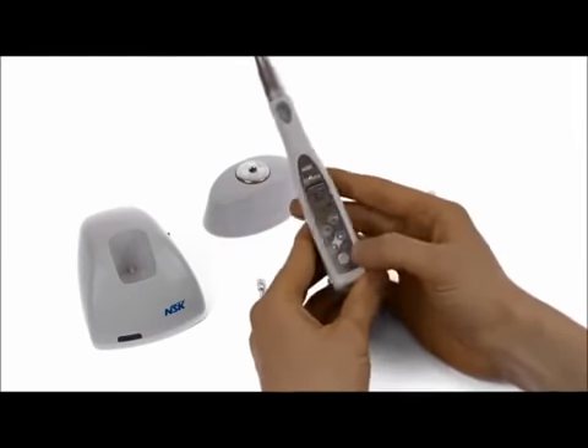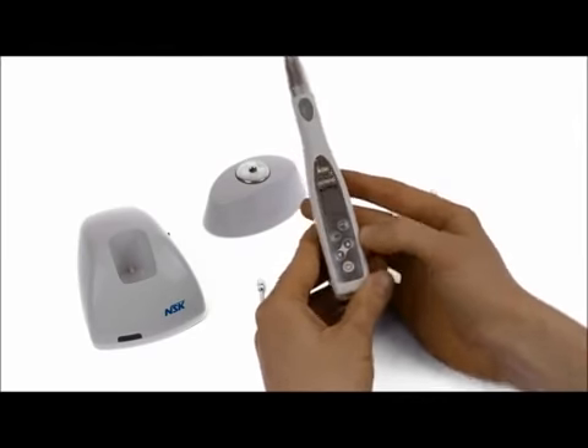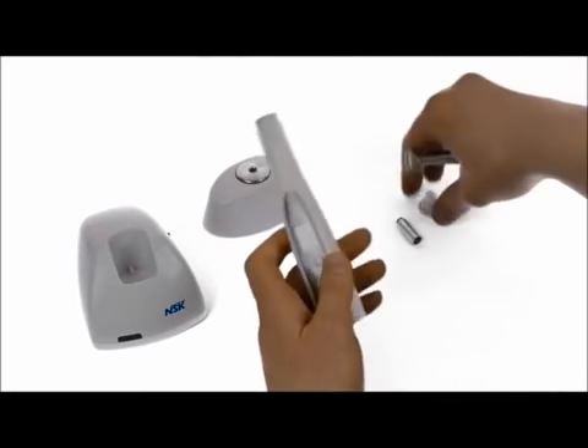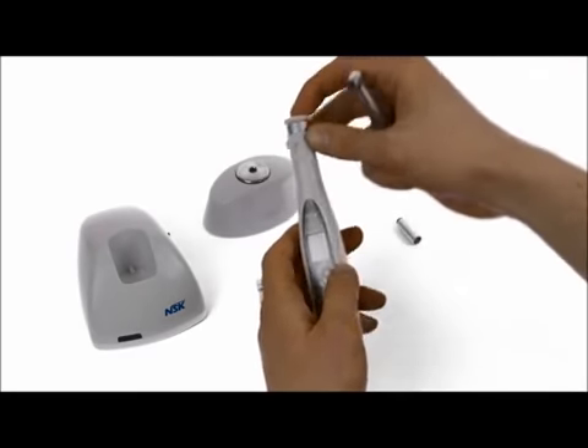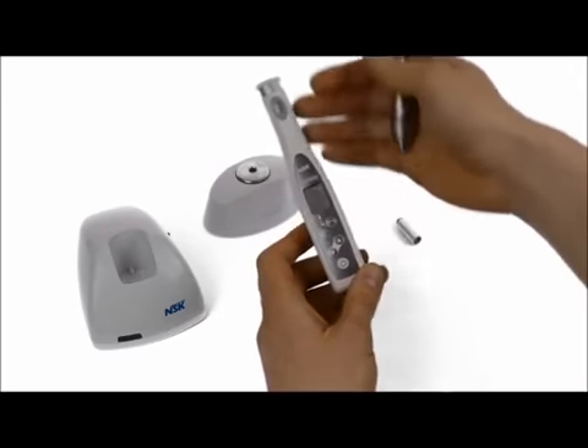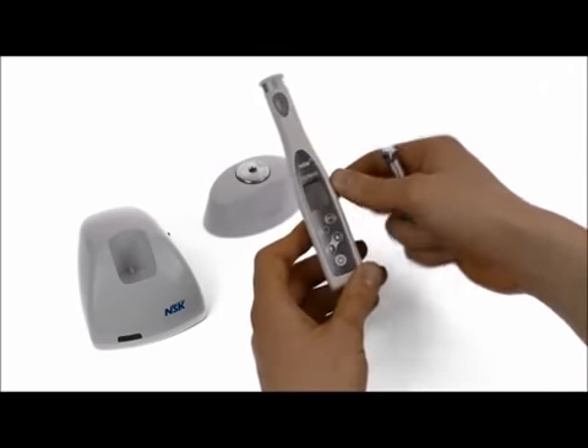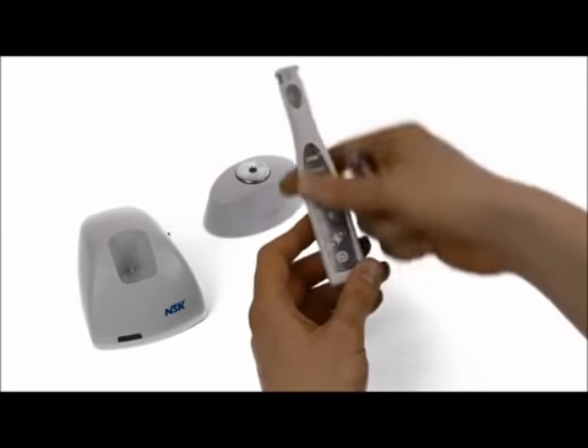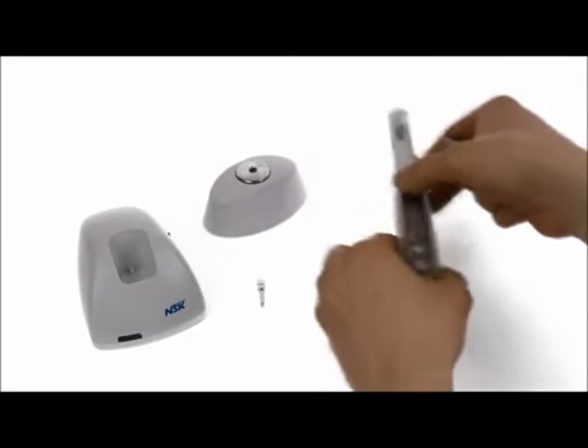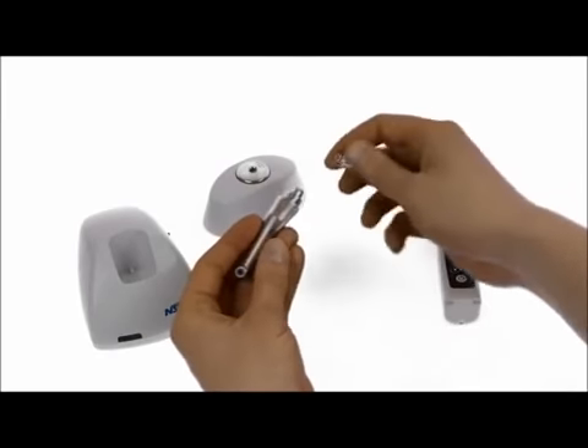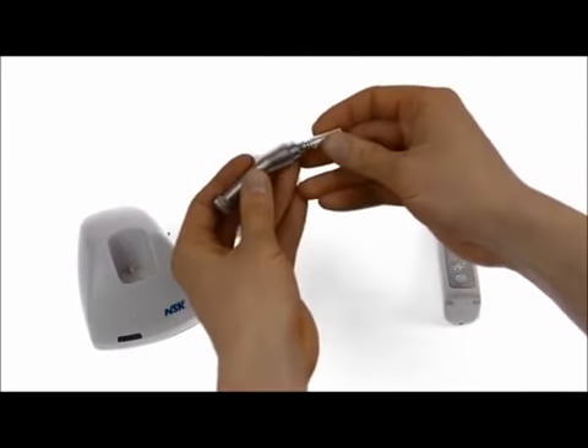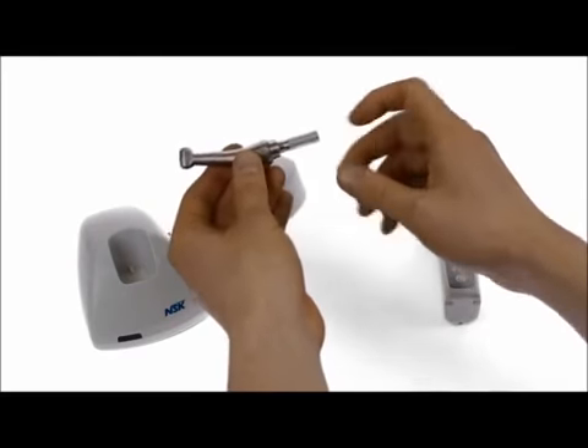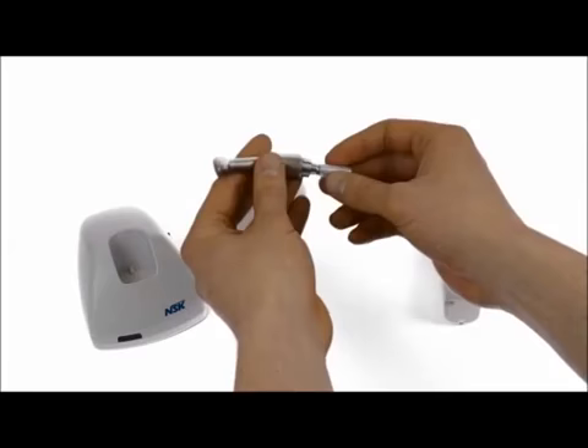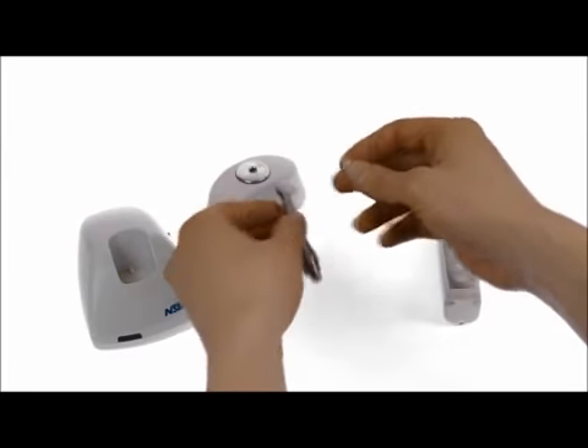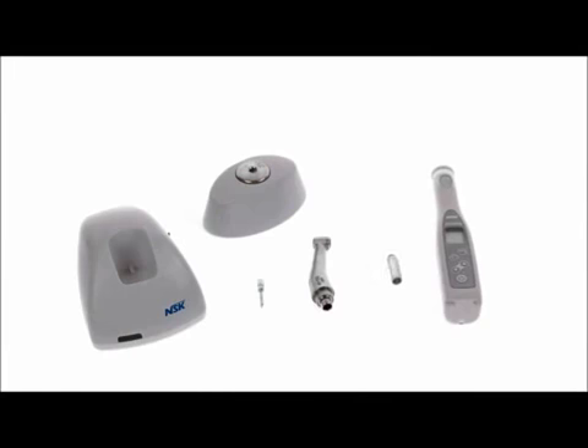So that's that. And then when you're finished, simply turn off the unit by holding the power button, disconnect the handpiece, replace the protective dust cover, and then you can wipe the unit down. We use it with a barrier across it, for easy cleaning. And then the sterilization staff can attach this to the motor, a couple of sprays of the handpiece lubrication oil for 2 seconds, and then disconnect that, and then that's ready for autoclaving.